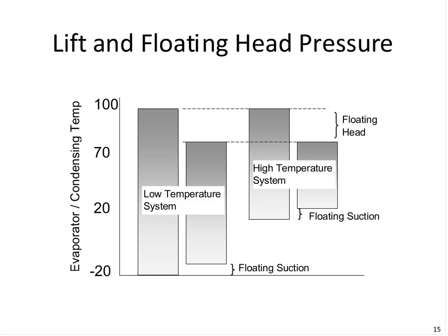So whether we're at minus 20 degrees or plus 20 degrees, with a low temperature system we might be at minus 20 or lower. Minus 40 is attainable with ammonia. If we want to go below minus 40, we would go to a different refrigerant, and carbon dioxide might be one of those. So from the lowest temperature, here we say minus 20, to our condensing temperature, say 95 degrees outside, this is known as lift. So from the lowest to the highest temperature.